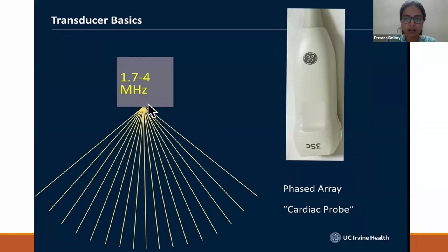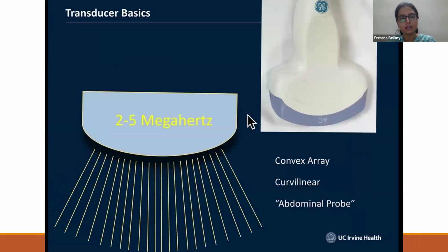Before the phased array, we will see the curvilinear or the convex array probe, also called the abdominal probe, best to visualize the abdominal structures and for obstetric and gynec scans. It's a low frequency probe, so it operates between 2 to 5 megahertz, and the crystals are arranged in a convex shape. So the image that we see is quite wider when we compare it to a linear transducer.